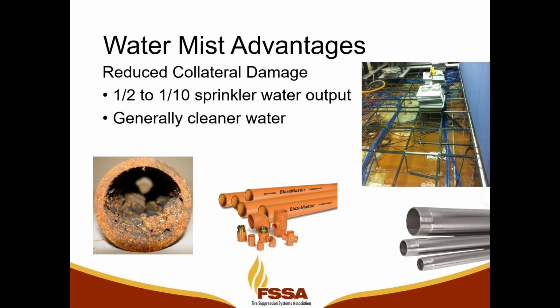When we're talking about a machinery space or a turbine enclosure where we're using a deluge system that's got an open head nozzle, where we're going to flow water through the entire nozzle network simultaneously, we're going to see as little as 1/10 the water output of a sprinkler system.